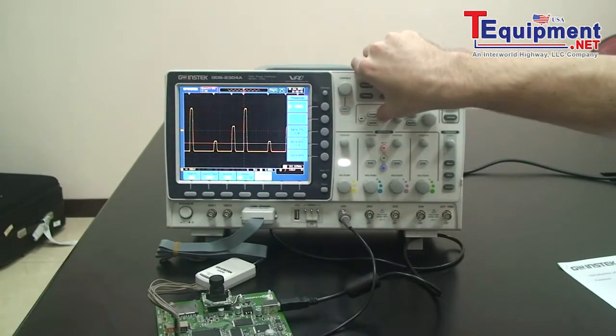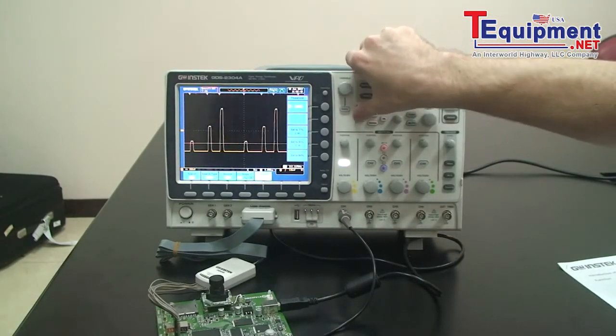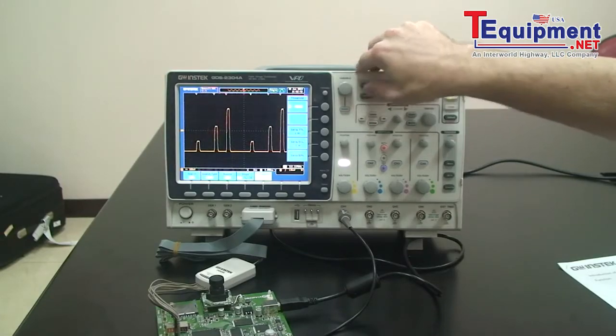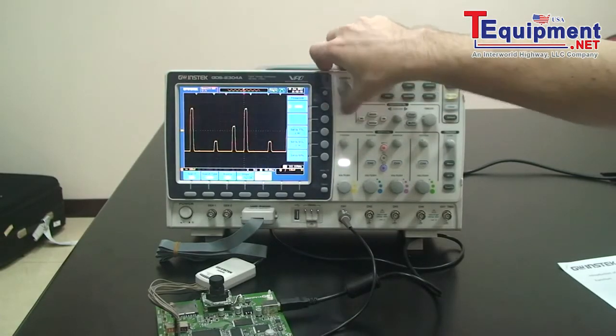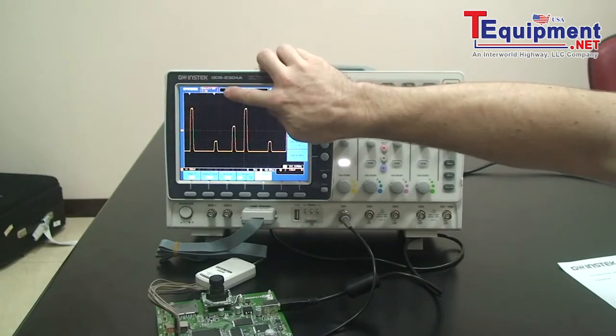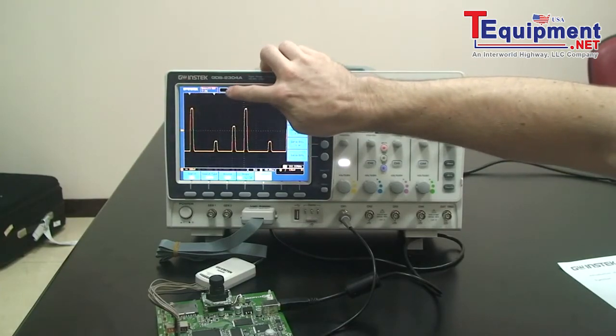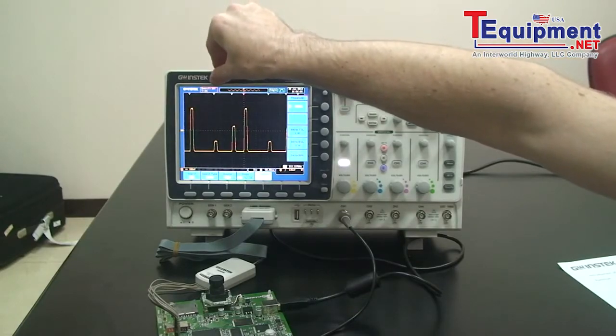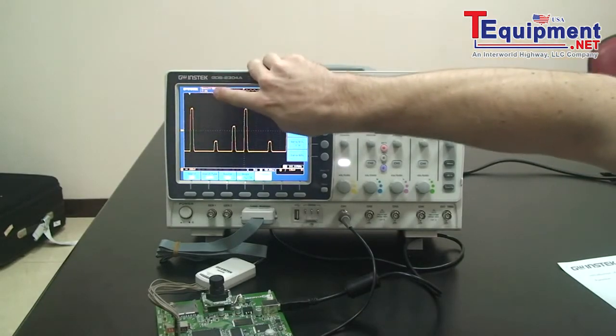We can use the left and right arrow keys to go through each event. At the top here, we have the status icon. It tells us how many events are captured throughout the whole memory length. In this case, it's 167, and currently we are on event number 84.